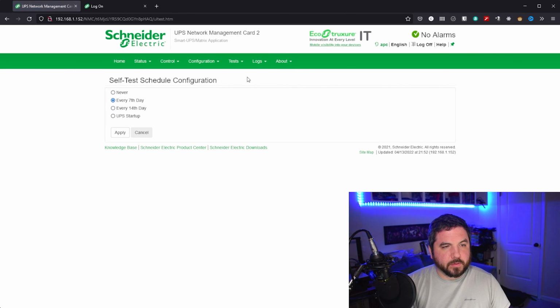The self-test schedule configuration page is where you can set your schedule for doing a UPS self-test. This is good to do. You could turn it off if you want, but it's not that intrusive. I would just leave it at either the 7th day, the 14th day, or even UPS startup would be a good option.